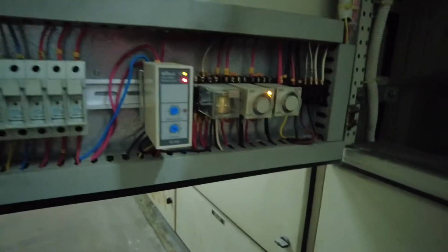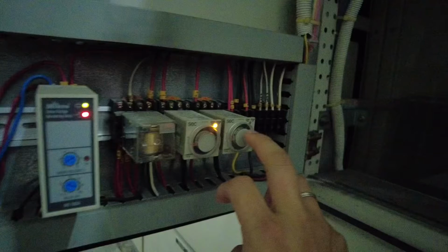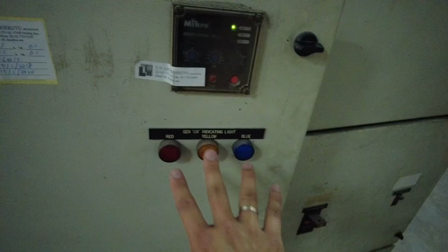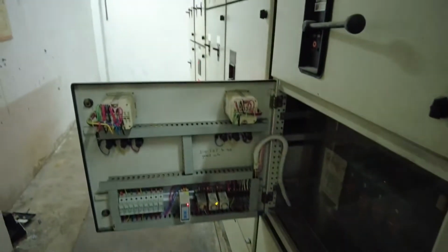Okay, first of all, we're going to test run the genset. Here we have the ATS panel. This is the ATS panel, and this is the UVR relay, the main supply timer, and the genset timer. As usual, we're going to test run the genset under off-load condition by triggering the genset from the ATS panel. Currently we have the main supply here, but the genset is under off condition. Before we test run the genset, we're going to check the genset first. Then we will run the genset by triggering it from here.